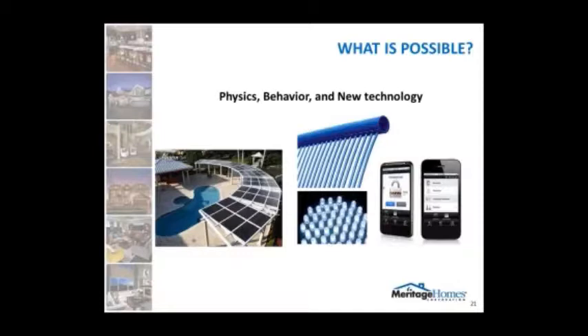So there's been a tremendous difficulty in hot and humid climates where we're making our homes so efficient through the lights and the windows reducing heat and the great insulation that when we bring in fresh air, the humidity doesn't have a mechanical way to be removed. And HRVs or ERVs actually exacerbate that problem. So we're doing a number of technologies to fix that, but the long and the short is you need to either bring in dry air through selective fresh air ventilation, or you need to dehumidify that fresh air.